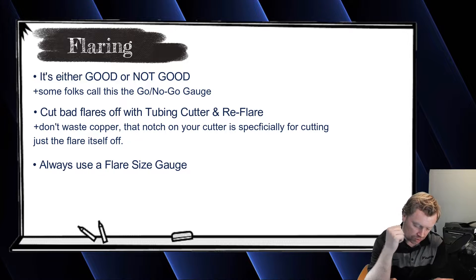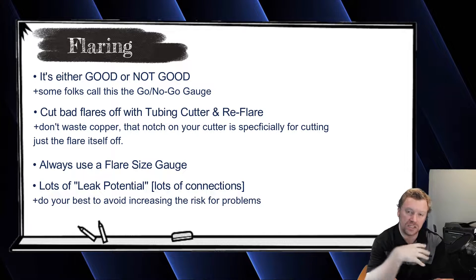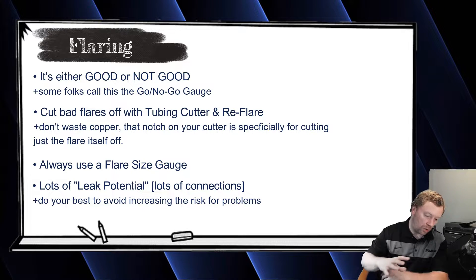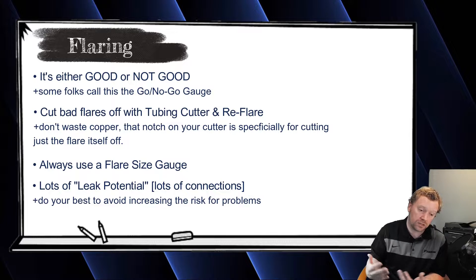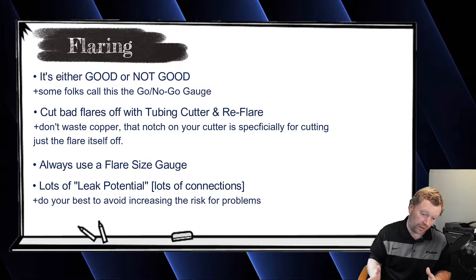In commercial work with two flares on each indoor unit and 144 indoor units, there's a lot of potential for a leak. In my market in Seattle we're flaring, though I've heard in markets like Chicago they have to braze everything. Regardless of your market, you just have to make sure to make the correctly sized flare — that's step one. Step two is torquing your flare.